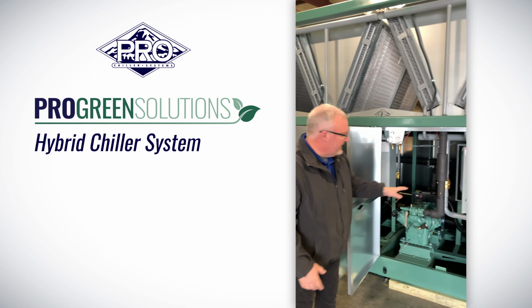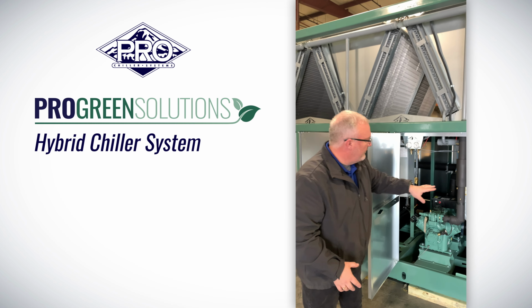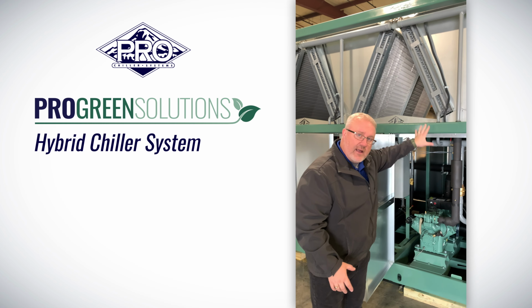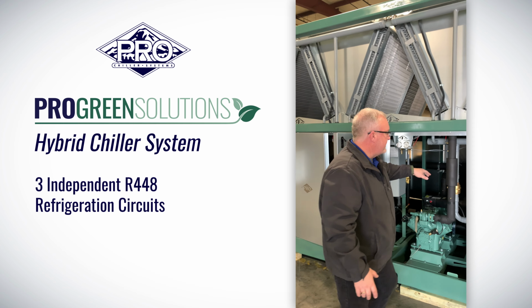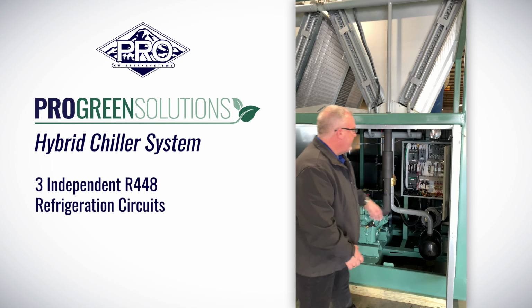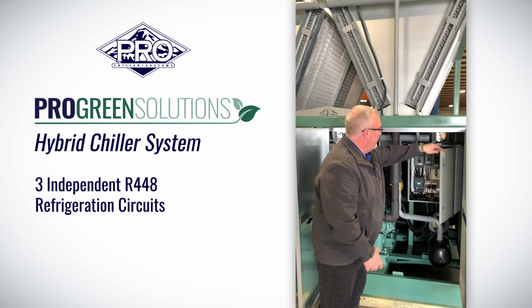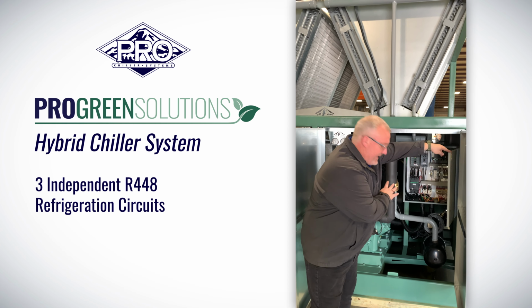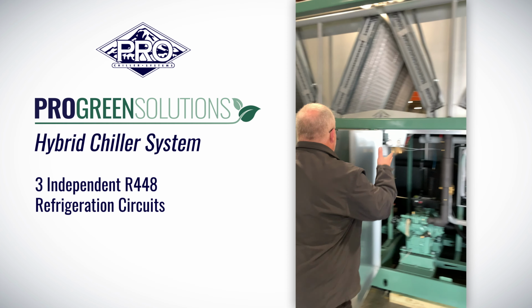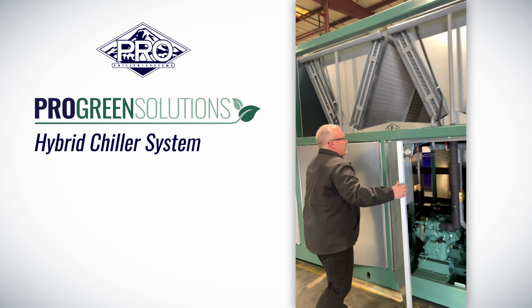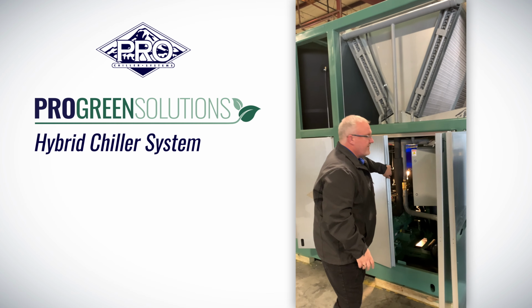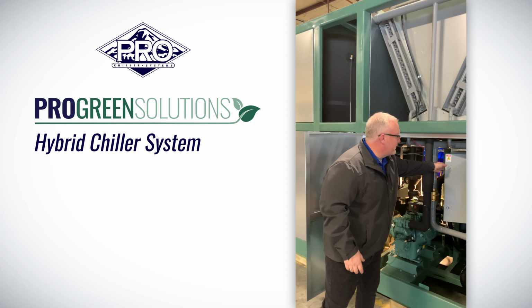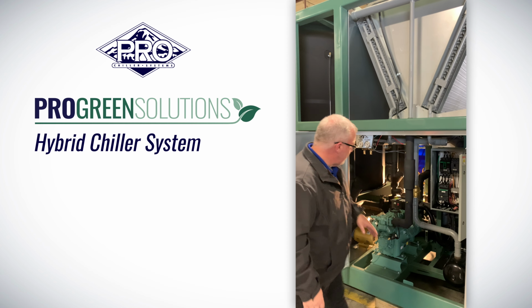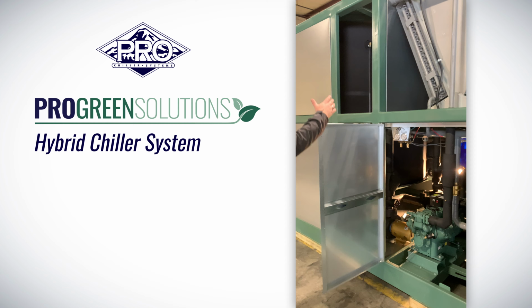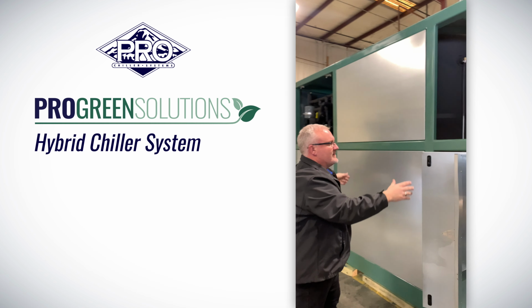Each circuit is built modularly, so we have a dedicated independent 50 horsepower refrigeration circuit, and the electrical control panel with the controls that focus just on this 50 horsepower circuit. As we work our way down, each circuit is built the same with all of our controls built inside. Over in this area, this is where our 2,000 gallon glycol reservoir is.